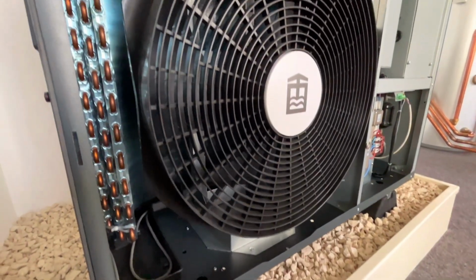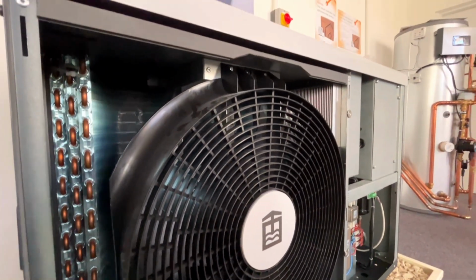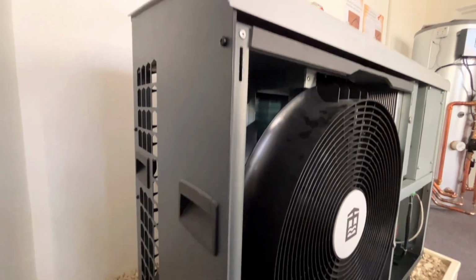Heat pumps can appear fairly magical, taking heat out of cold air to heat a house. But as Tom talked through and showed us in the factory, they can be quite simple, and Ebac's heat pump is no different. There's a fan to draw air over a heat exchanger, which takes heat from the air to deliver it to a refrigerant that's then evaporated by that heat. The refrigerant is then compressed using some electricity before dumping the compressed heat, all that energy, where it's needed in a hot water circuit.